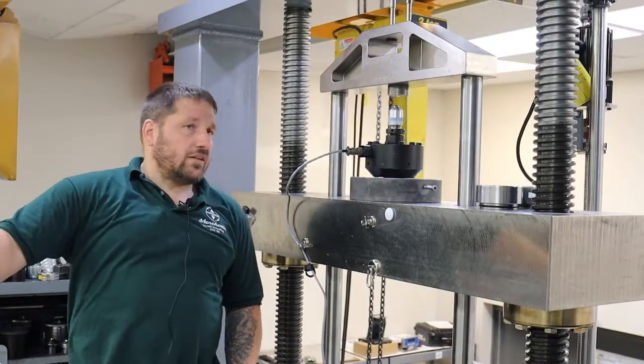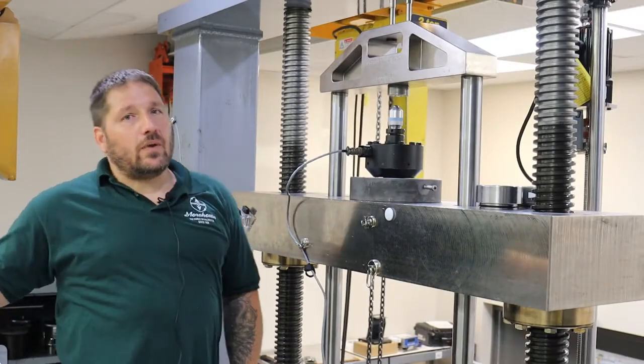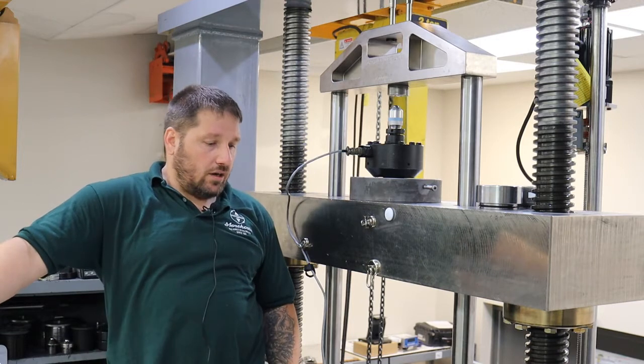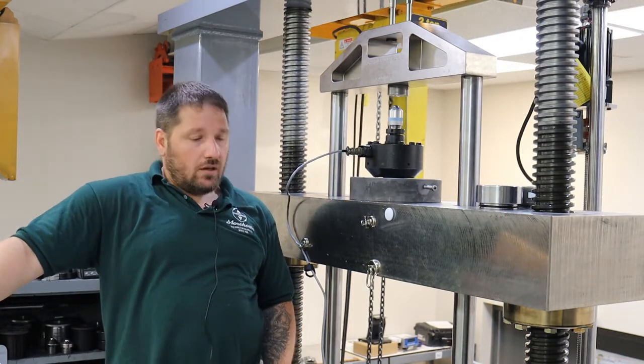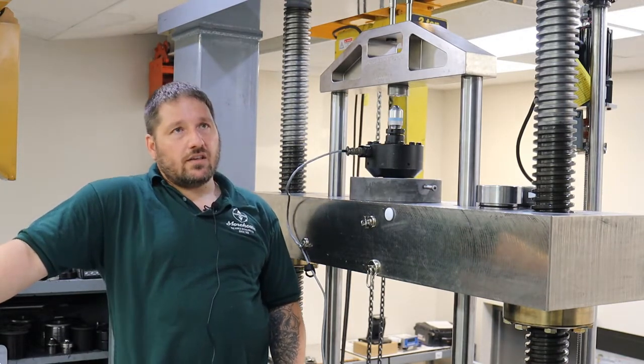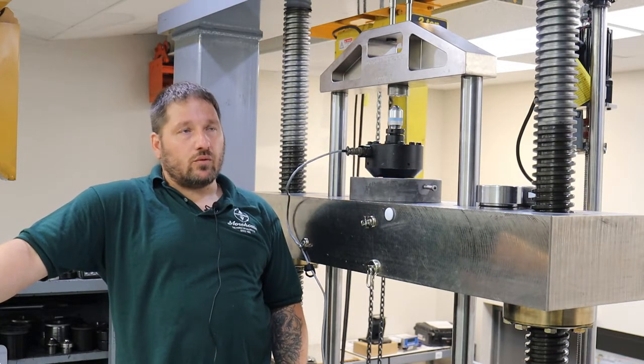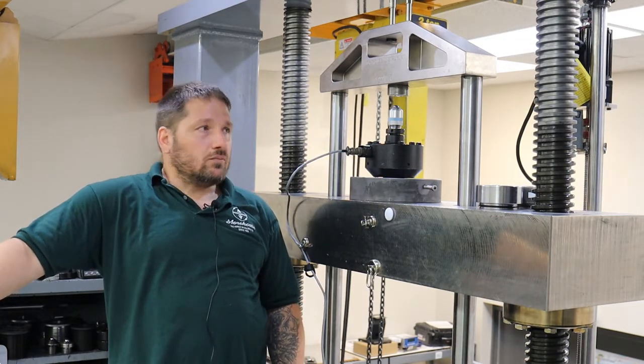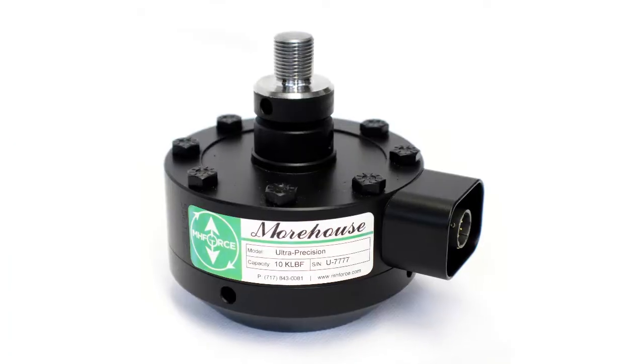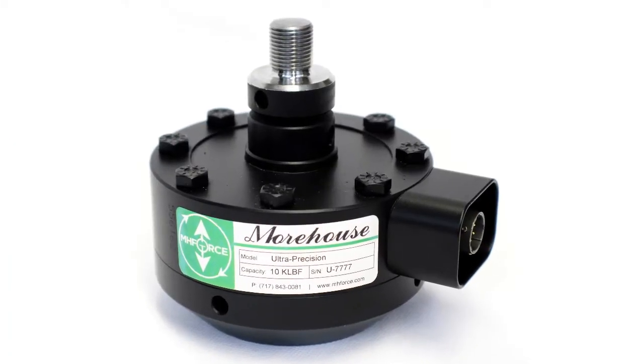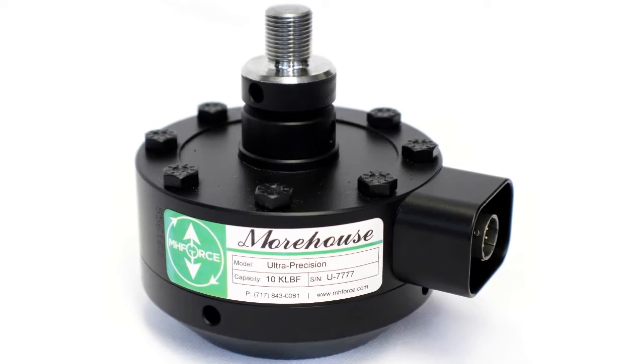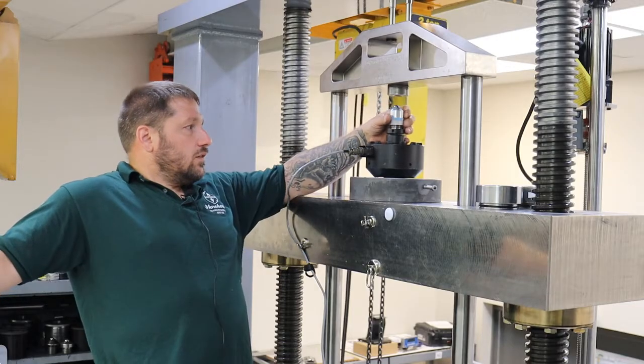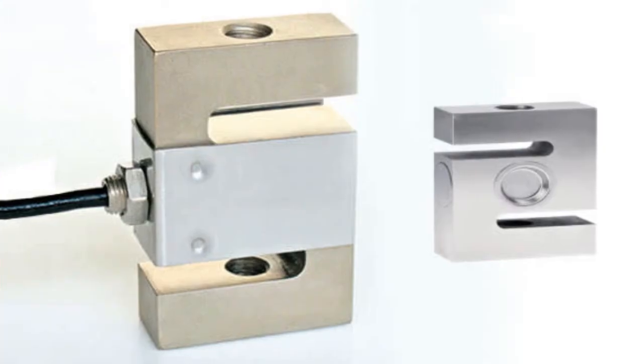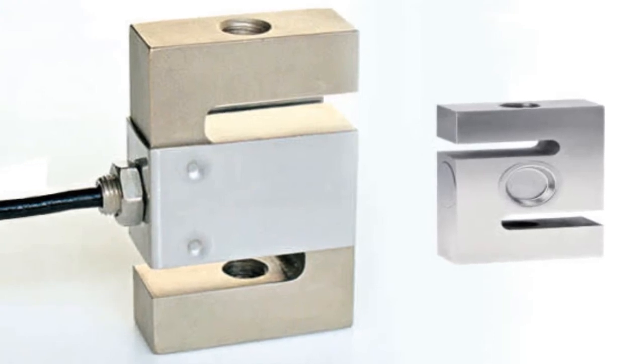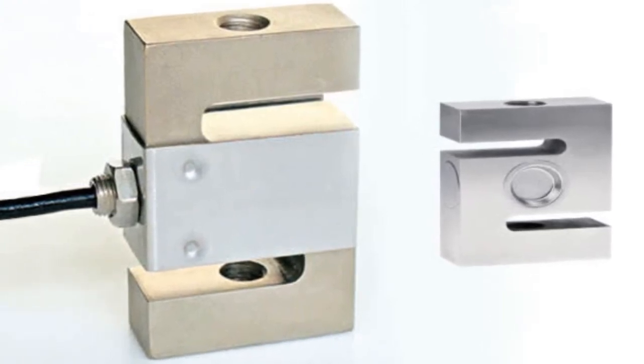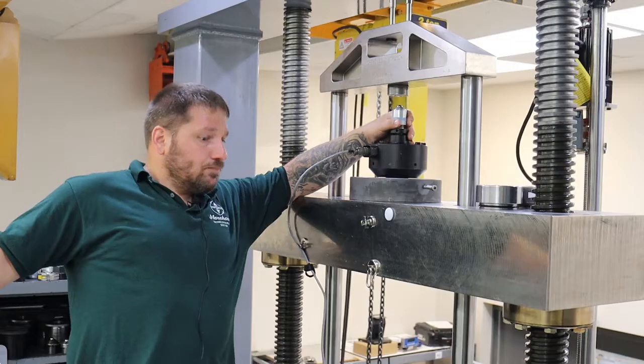Okay, so we're going to talk about the difference between loading against the base and thread loading the bottom of the load cell. Either way is not necessarily wrong. There would be some instruments I would recommend one or the other. Like a shear web like this load cell, I would recommend to load directly against the base. But other things like S-beams, some S-beams, I would thread load them top and bottom. But we're going to show you the difference here today.